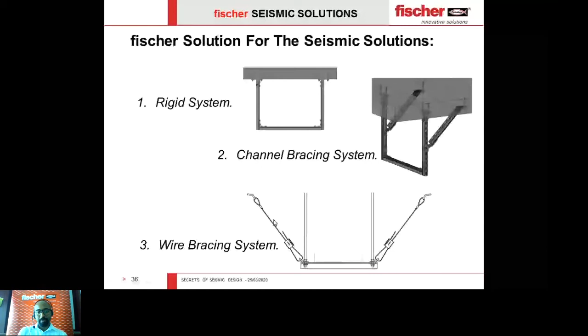So the rigid system looks like this. Upon seismic analysis, we determine the spacing between two seismic supports, and then we provide the rigid system. As you can see here, it is a rigid system for a cable tray, and on the bottom right side is a close-up image. In this case, the seismic support needs to be installed at the same time as the normal support.